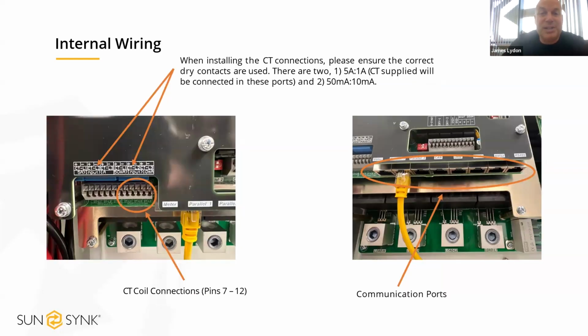So the standard CT, if you use the CTs that are supplied with the inverter, on the image on the left you can see we've got the push fit connections there. They will be connected there. And then if you are using the Eastron meter, on the image on the left as well, you can just see the meter port there. So that will be connected into there on an RJ45.